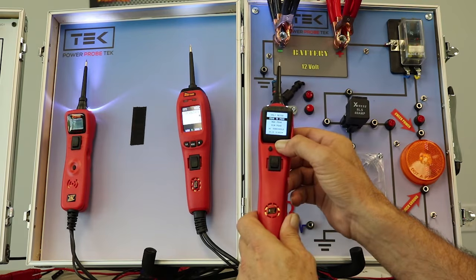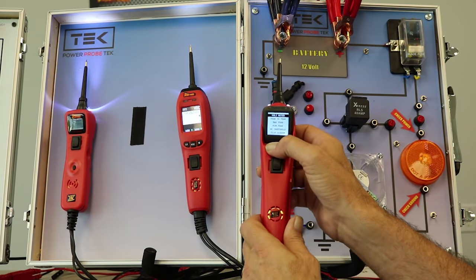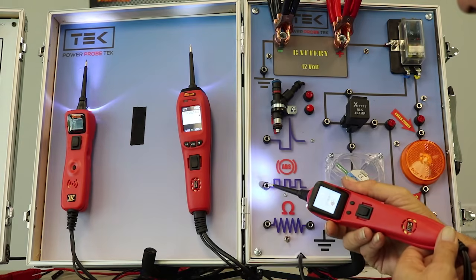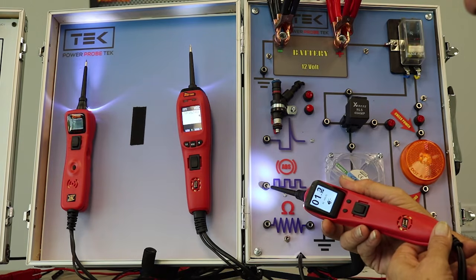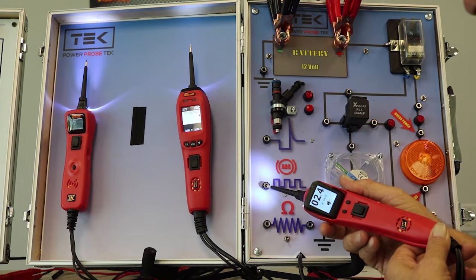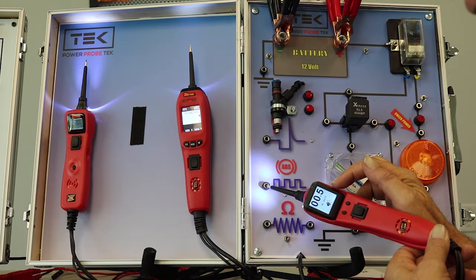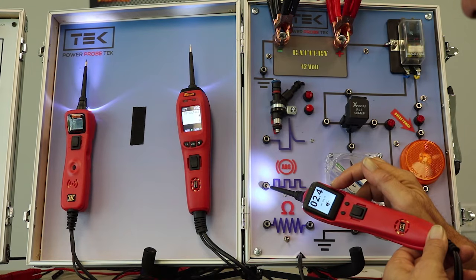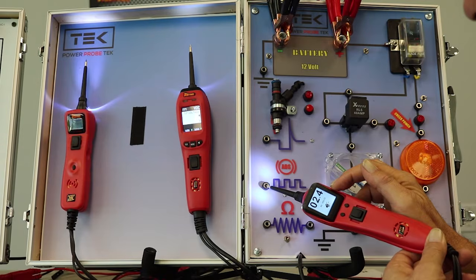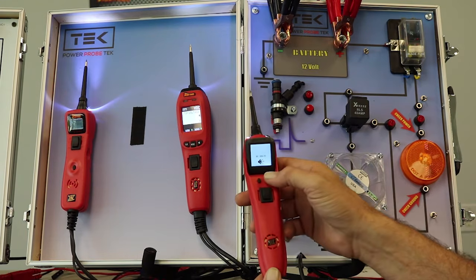Now let me put it back in normal DC voltmeter mode. This is a 5 volt pulse I'm tapping onto here, and the response is a little erratic. I've got a very short pulse, so it's having a hard time picking it up. It's trying to average it to about half the voltage, 2.4 volts, and most traditional meters will do that same thing.